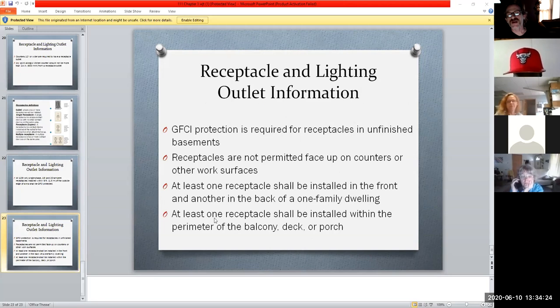And you have to have at least one receptacle, shall be installed, within the perimeter of any balcony, deck, or porch. So if you do a little deck upgrade to your house or something like that, and you have no receptacle within that deck area, you're in violation of code. But the little things we learn.